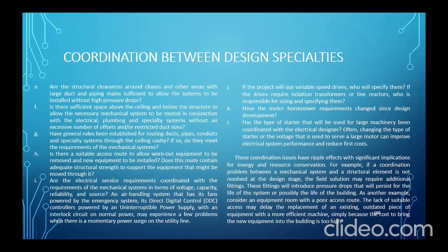E. Are the structural clearances around chases and other areas with large duct and piping mains sufficient to allow the system to be installed without high pressure drop? So, di ka yung malaki yung duct mo kasya. Di ka mapilitan na paliitin. So F, is there sufficient space above the ceiling and below the structure to allow the necessary mechanical system to be routed in conjunction with electrical, plumbing, and specialty systems without an excessive number of offsets and or restricted duct sizes? So, maluwag ang area mo sa kisame. Papalagay ng ducting, wala namang daanan sa kisame.